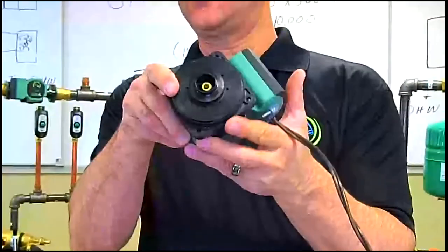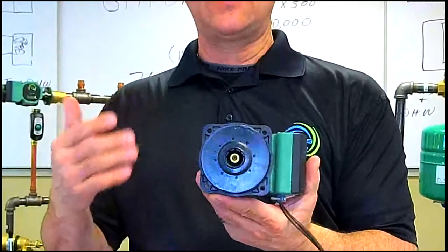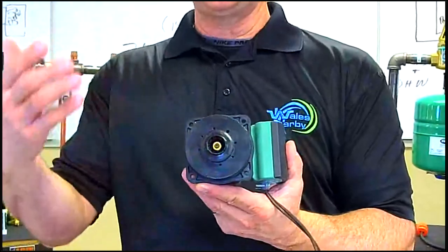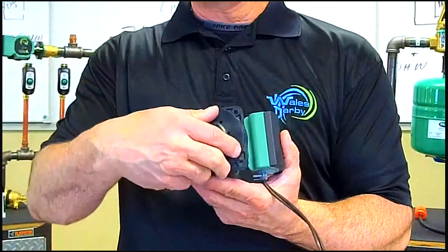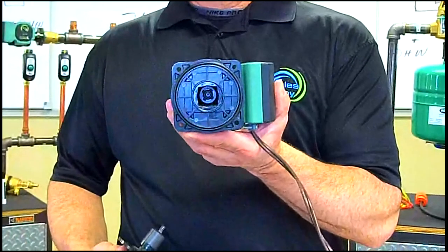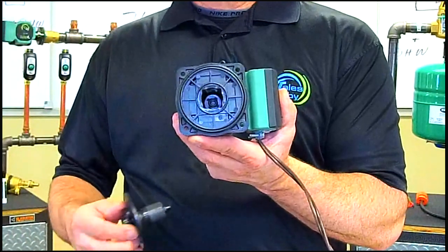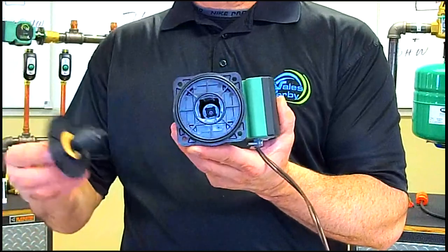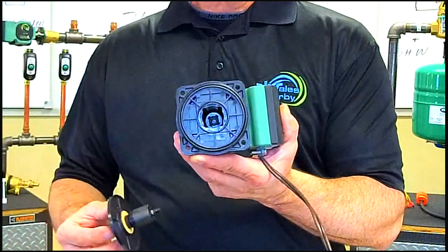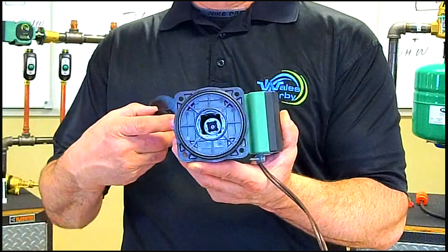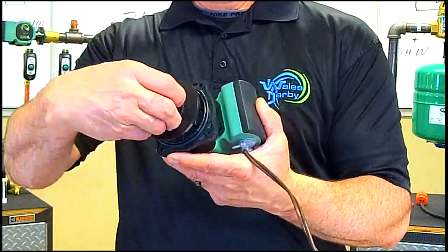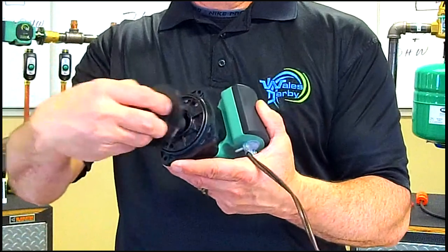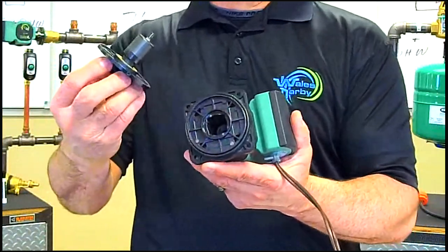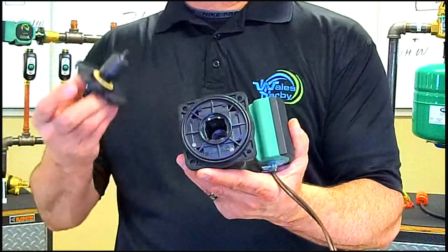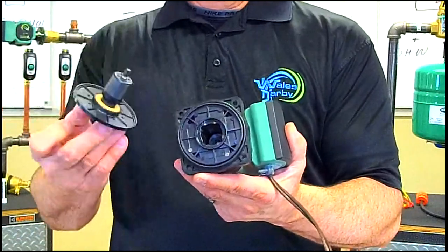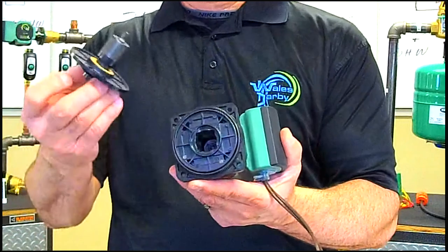This is the eye of the circulator. How all of these wet rotor circulators work is the first time you put water to a system, water goes in through the eye and fills this inner portion. And this is no different on a standard 007, 007E, all of them, they work the same way. The difference with the ECM versions is this rotor is magnetized. Okay, so it's a permanent magnet. So with an AC motor, we have to rotate the motor to create magnetism. Here, we have a permanent magnet. This is why we run lower wattages, because we have a permanent magnet.